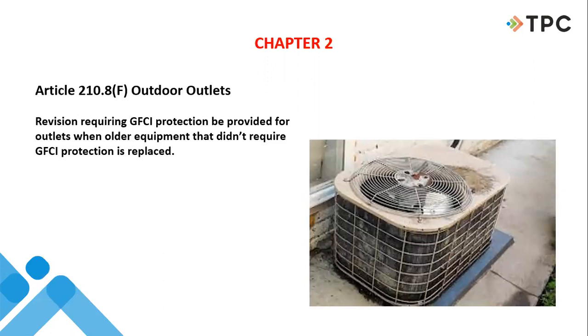You have old AC equipment like this sitting outside, been installed for quite some time. At the time that it was installed, it didn't require ground fault protection for anything. Well, this revision now requires ground fault protection be provided for outlets whenever older equipment that didn't require it is replaced. Kind of a reverse grandfathering thing. You're going to install a new unit, going to bring it up to date, you've got to bring the ground fault protection up to date with it.